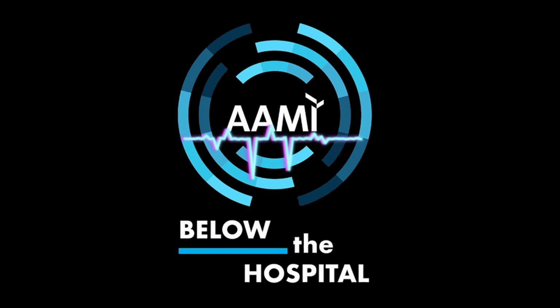Speed and device turnaround have become a major focus, and so the standard of care has become hydrogen peroxide. They've got the cycle time down, unbelievably. I mean, 20 years ago, who would have thought you'd have a sub 30-minute sterilization cycle? Automated endoscope reprocessors are going to remain the standard of care for endoscope reprocessing.